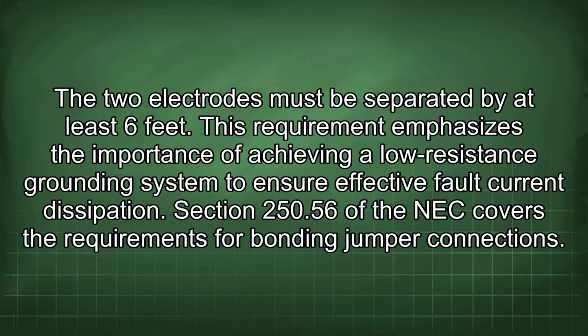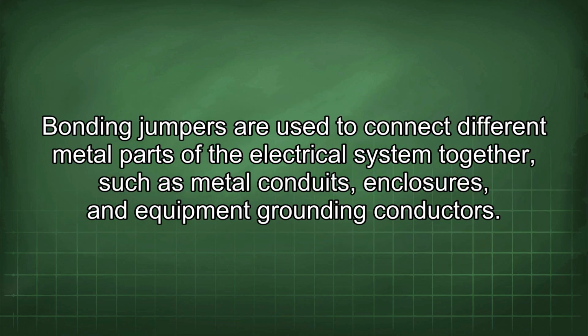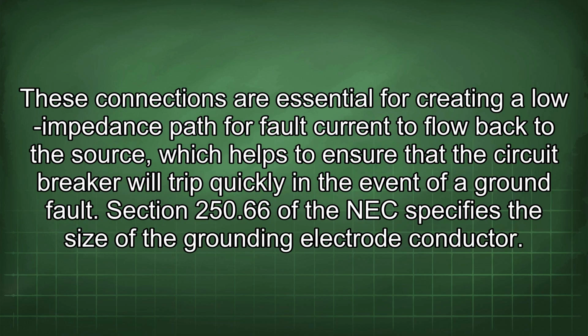Section 250.56 of the NEC covers the requirements for bonding jumper connections. Bonding jumpers are used to connect different metal parts of the electrical system together, such as metal conduits, enclosures, and equipment grounding conductors. These connections are essential for creating a low impedance path for fault current to flow back to the source, which helps to ensure that the circuit breaker will trip quickly in the event of a ground fault.